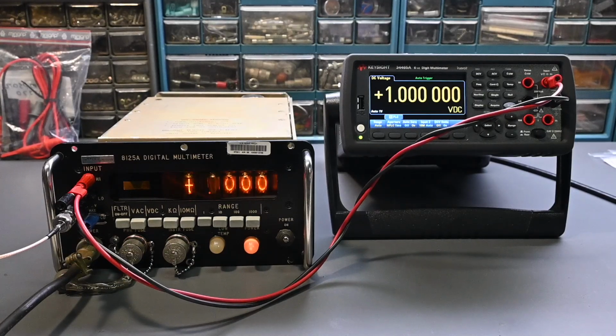Now, I noticed that in doing the calibration, every single calibration point needed some touching up. Some were a ways off, but none of them were wildly out of spec. But again, everything did need some touching up. So I think that sticker that we saw on the front panel that said that the instrument had been calibrated probably many, many years ago, I think it was accurate. It probably had been calibrated, but it's interesting that it had such physical damage, with the bent metal and the other issues going on, but yet still seemed to be calibrated, and it was rather close.